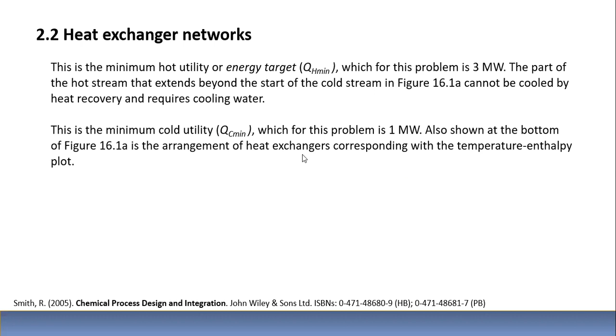And since the cold stream was going from 40 all the way to 110, having a vertical line of minimum delta T beyond this to the left, then you require a minimum amount of energy to be absorbed by a cooling tower. And likewise here to the right, where these two streams do not overlap, you require a minimum amount of energy as input into the process, as live steam that is coming from a boiler. This is the minimum hot utility, and the minimum cold utility we saw to the left. Also shown at the bottom of figure 16.1a is the arrangement of heat exchangers corresponding with the temperature enthalpy plot, which is this arrangement which we saw a few minutes ago.